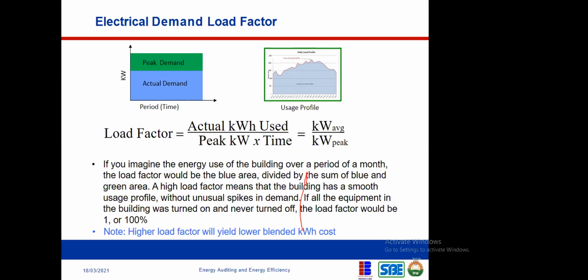This time here is assuming you're looking at your load factor for a day. If your load factor is the amount of energy you extract from a particular generator - if you have a generator, let me put this in simple terms - if you have a generator of maybe 20 kVA and you're only using 10 kVA out of that capacity, then your load factor will definitely be the 10 kVA divided by the 20 kVA, which is the actual peak capacity of that generator. I'm putting this in the context of a generator, but in the slide here it is put in the context of a peak load. So your load factor is your actual energy used divided by the peak load times time. This peak load times time is the total amount of energy you can actually get out of that system.